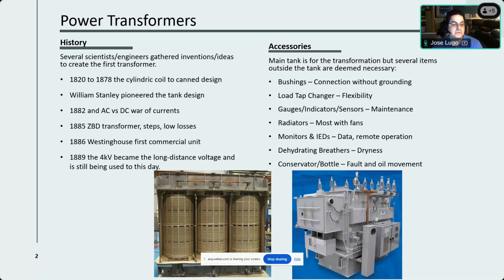There was a transformer called the ZBD transformer, which was very important when it comes to power transformer designing. That's because they created steps, basically connections within these huge windings in different locations, to give you different values of voltage. So you can use a mechanism called a load tap changer that will change the voltages for you.